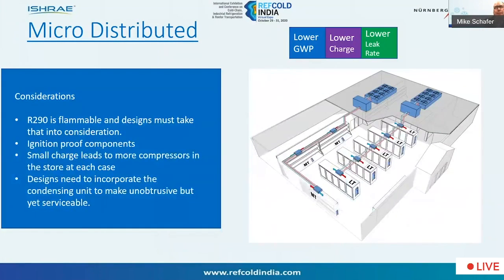So what are the considerations? Well, R290 is flammable, and so that obviously needs to be taken into account. These systems typically would have ignition-proof or ATEX rated components. Since there's going to be multiple condensing units per case, there's going to be more compressors and components in the store. And the designs really need to take that into account in terms of being able to incorporate the condensing units, make them unobtrusive, but still make them serviceable.